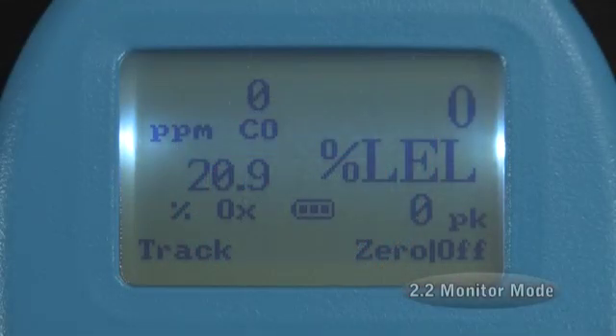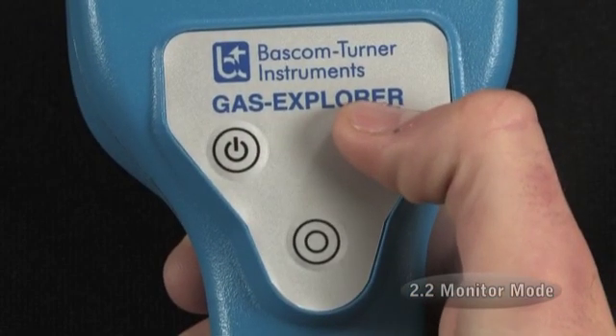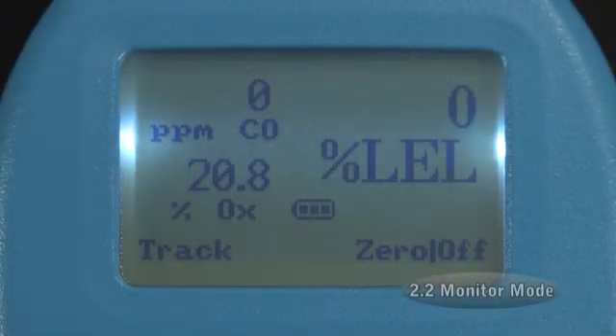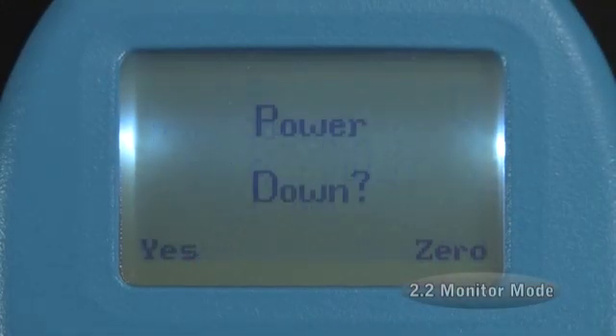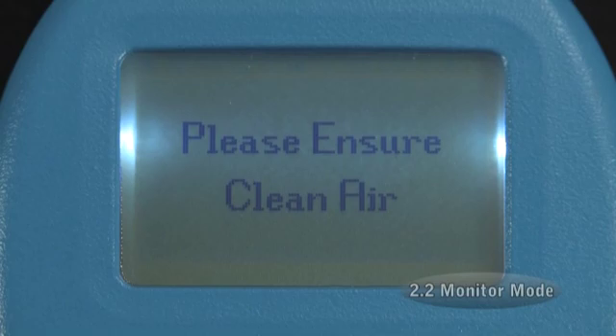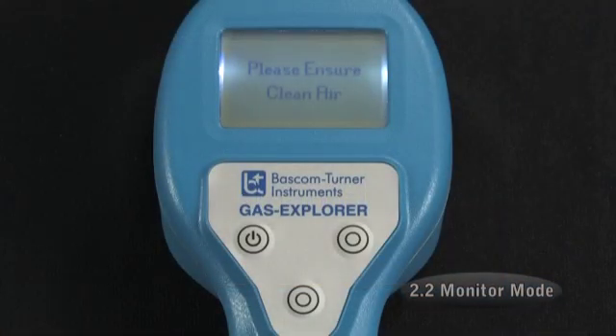In the lower right of the monitor screen, you will see two options, Zero and Off. When you press the right-hand button below those two options, you will see a new screen with the question, "Power down?" If you want to power down, press the left-hand button below the word Yes. If you want to re-zero the instrument, press the right-hand button below the word Zero. The screen will ask you to ensure clean air. You cannot zero this unit in a suspect atmosphere, and the unit will not let you do so.